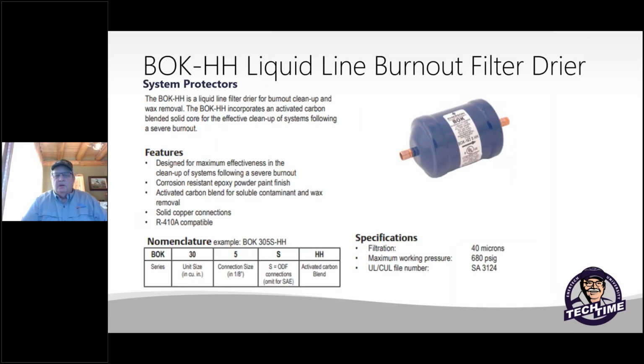One interesting thing a lot of people don't know: if you see this BOK-HH, it happens to be an Emerson burnout filter dryer. The HH designates that it has activated carbon inside of it, the blended solid core, to help clean up systems following a severe burnout. Filter dryers are manufactured by many different manufacturers as well. I have a couple of examples here, but I want you to pay attention that Emerson does not make an HH yet for geothermal heat pump or air source heat pumps in the HH category.